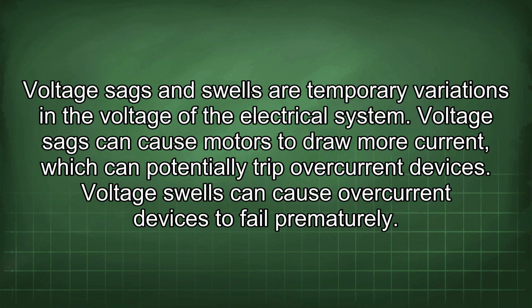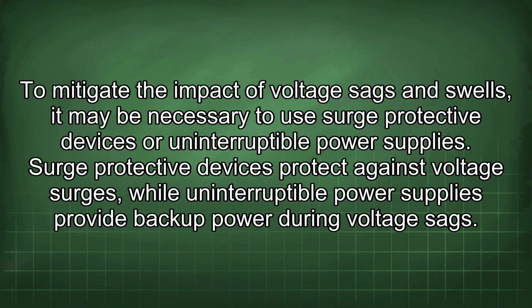Voltage sags and swells are temporary variations in the voltage of the electrical system. Voltage sags can cause motors to draw more current, which can potentially trip overcurrent devices. Voltage swells can cause overcurrent devices to fail prematurely. To mitigate the impact of voltage sags and swells, it may be necessary to use surge protective devices or uninterruptible power supplies. Surge protective devices protect against voltage surges, while uninterruptible power supplies provide backup power during voltage sags.